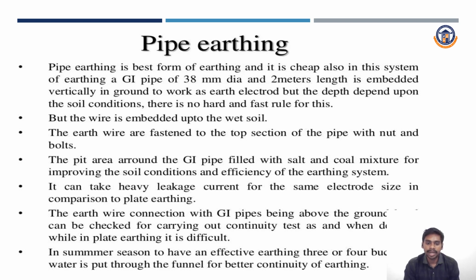The earth wire connection with the galvanized iron pipe, being above the ground level, can be checked for carrying out continuity tests, whereas in plate earthing this is difficult. In summer season, for effective earthing, 3 or 4 buckets of water are poured through a funnel for better continuity of earthing.